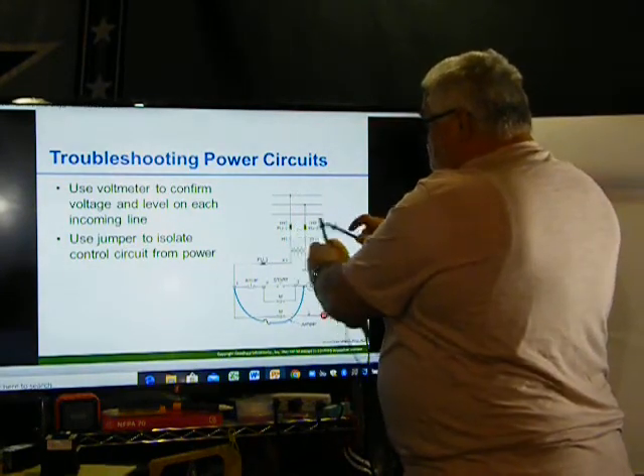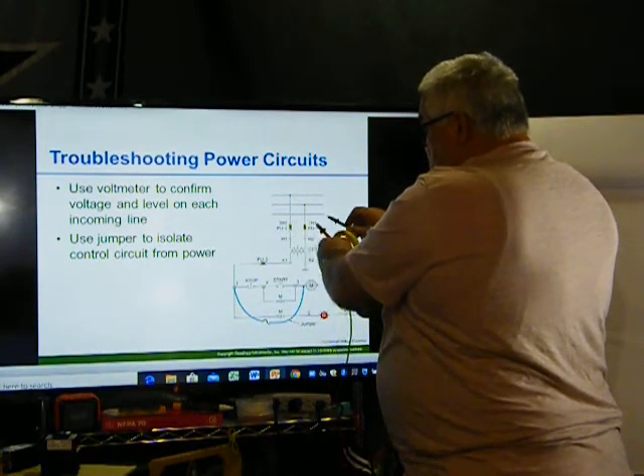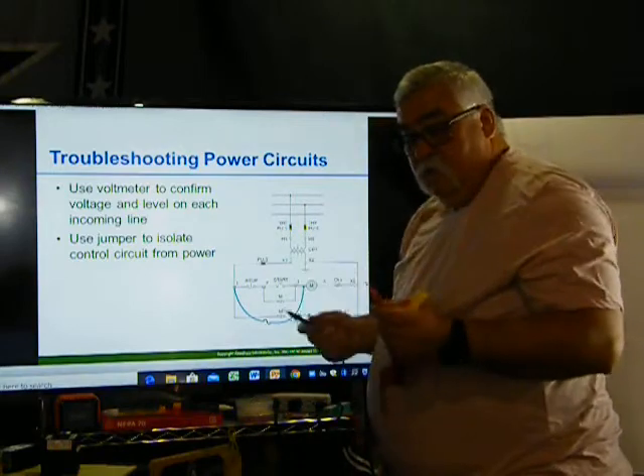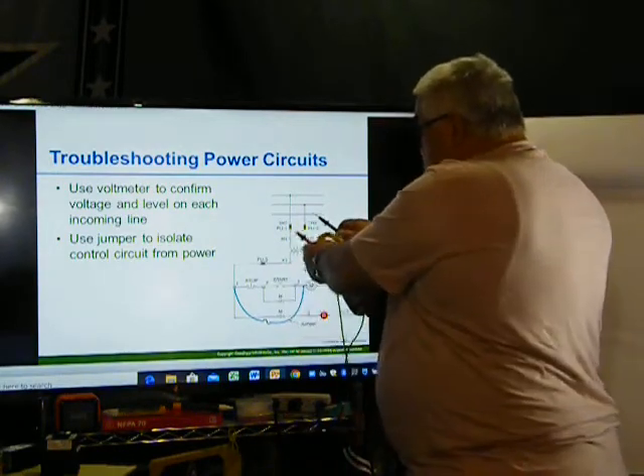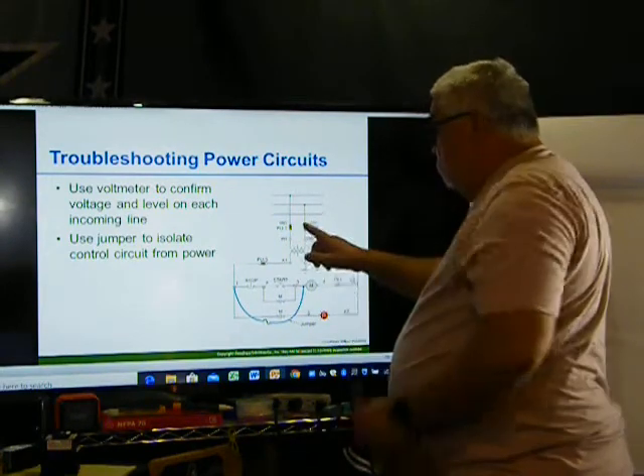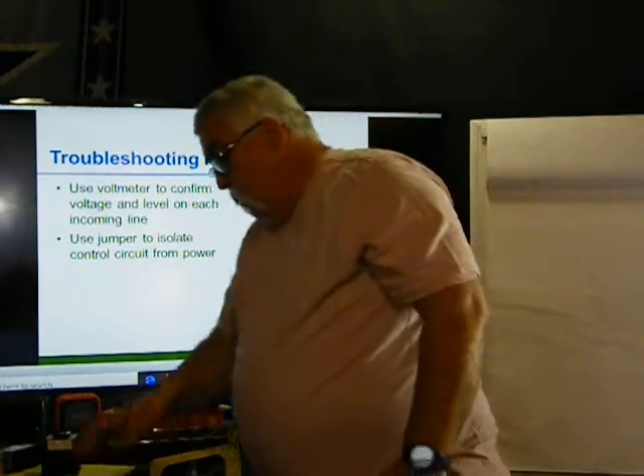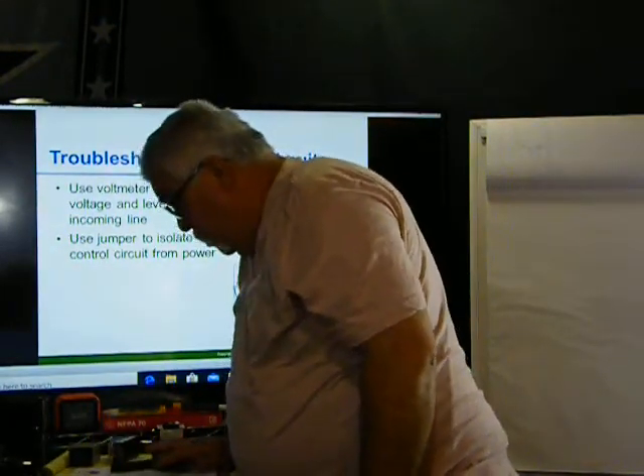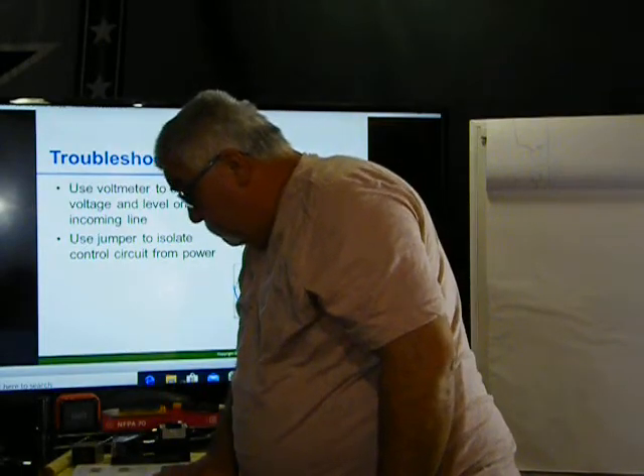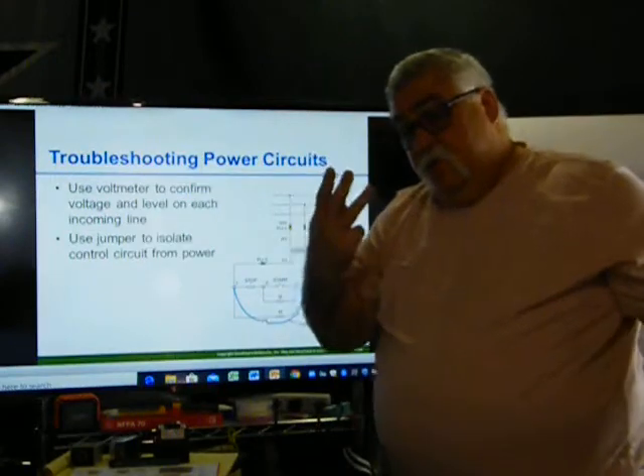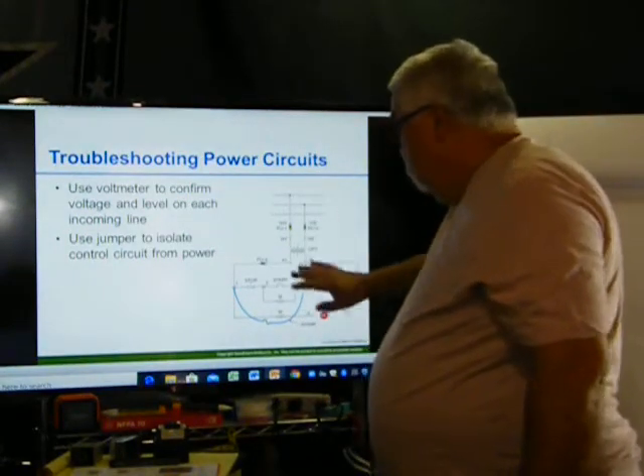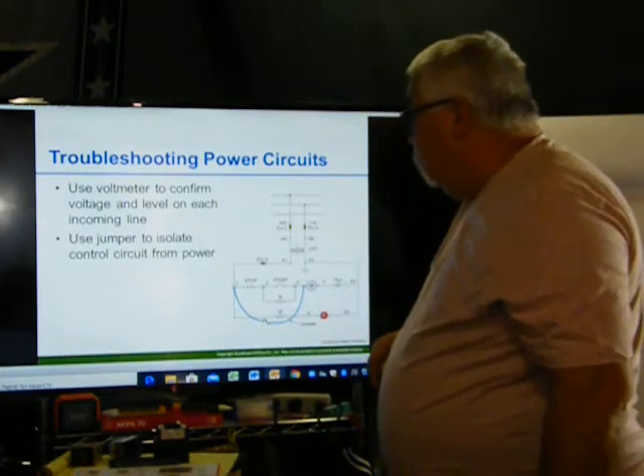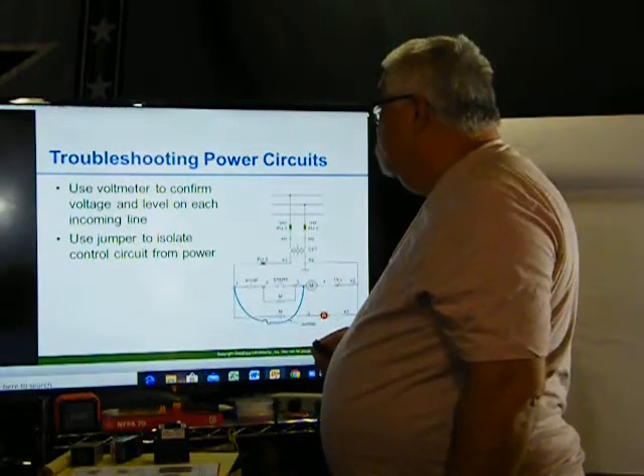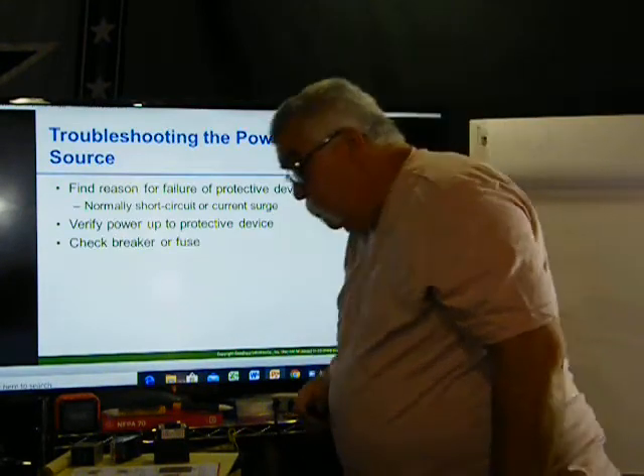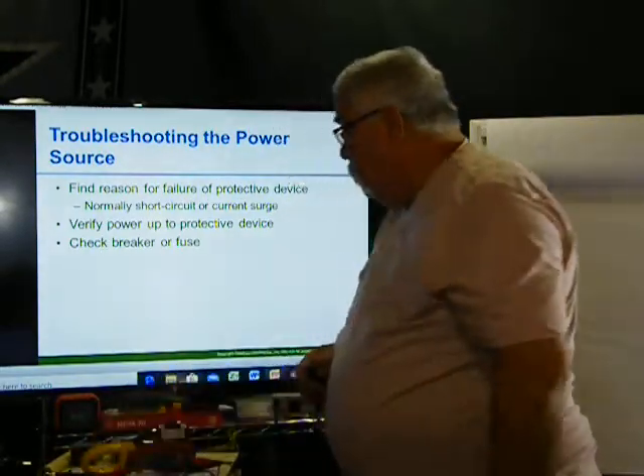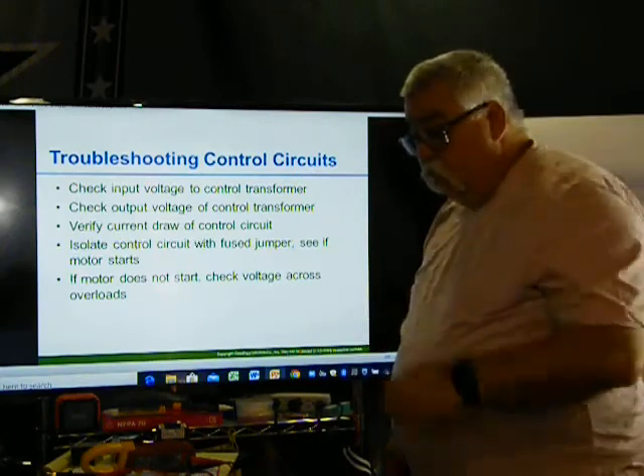Okay, I can go from the ground to the hot, to the hot. If I'm getting 240, 240, it's good. 240, 0, my fuse is bad. Okay, and on figure 18.1, when you look at it in your book, all they did is just what I did. Because they've got three phases, they're going across all three and doing it again. Here, control voltage. We'll get into the control voltage later. That's the next one. We're up to troubleshooting the power source, so making sure our power source has power. Troubleshooting control circuits, we'll do that tomorrow.